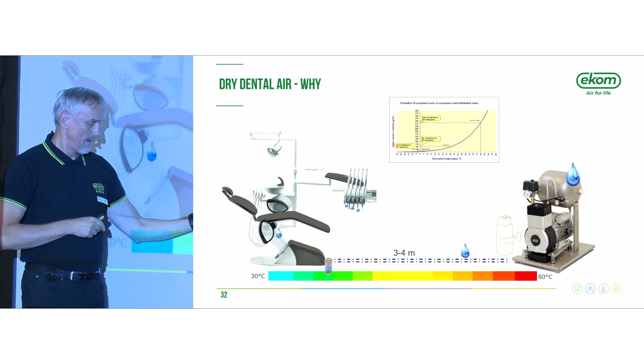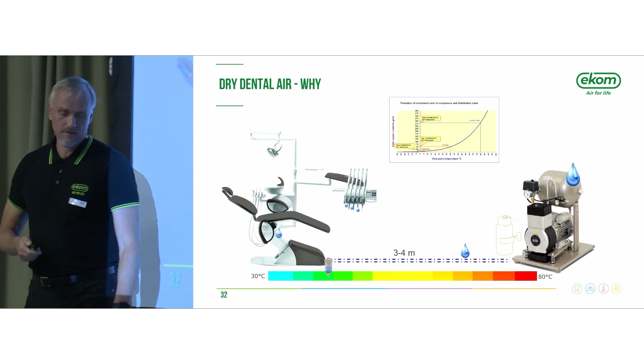Sometimes it is recommended, and I strongly recommend, just for that case, to assemble a water trap at the dental unit inlet, so that the water resulting from condensation will be captured in that water trap. This is a good point.